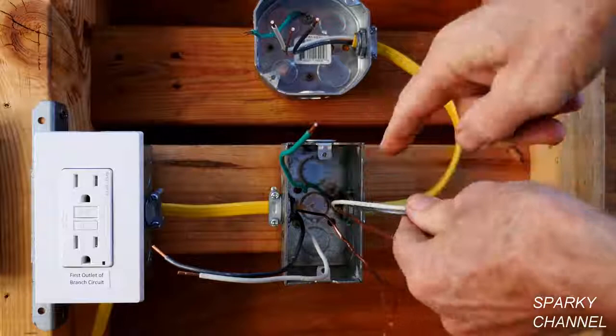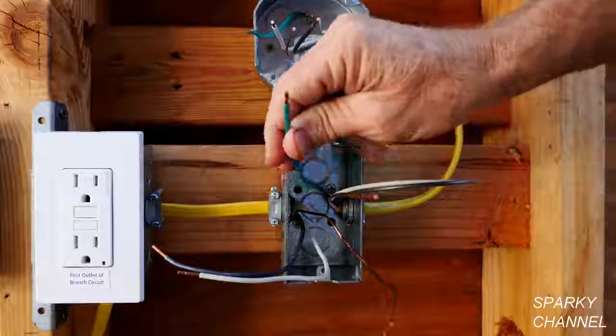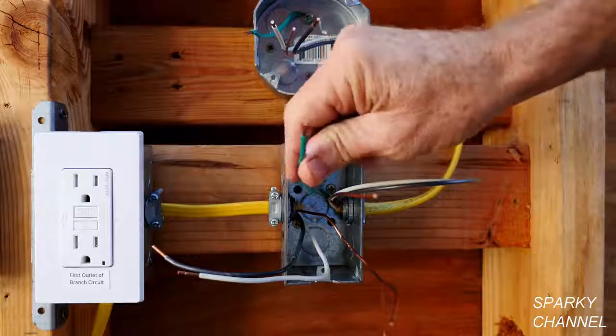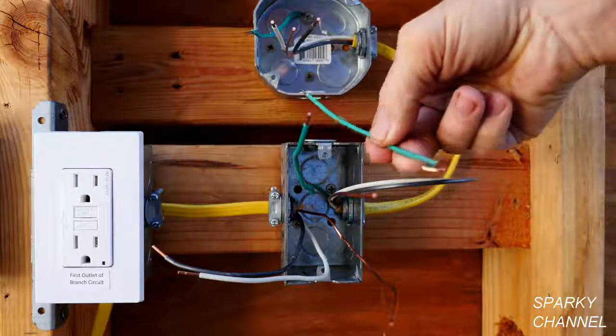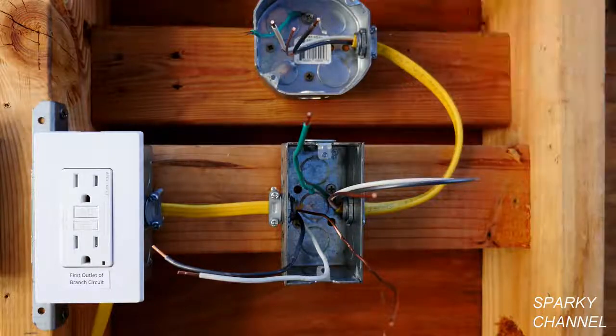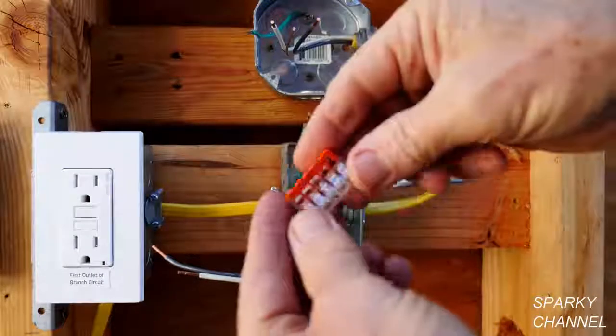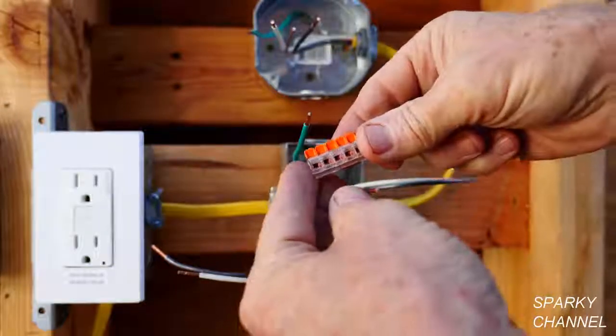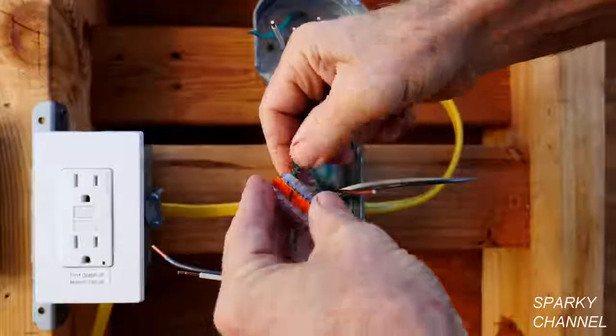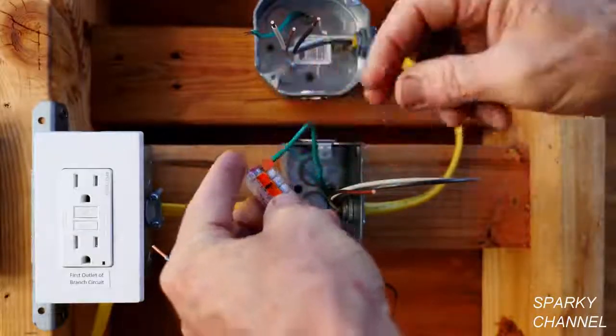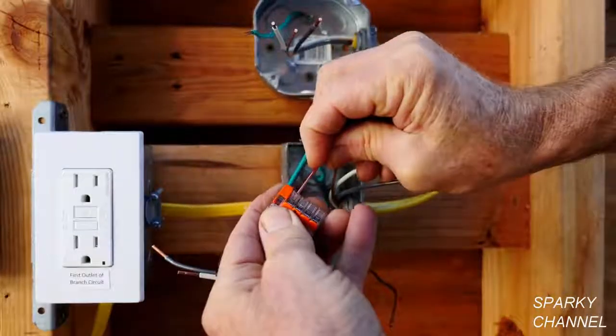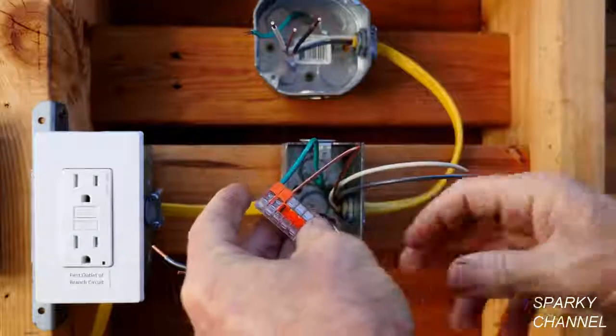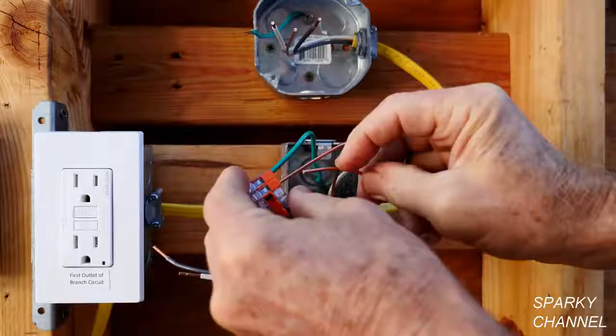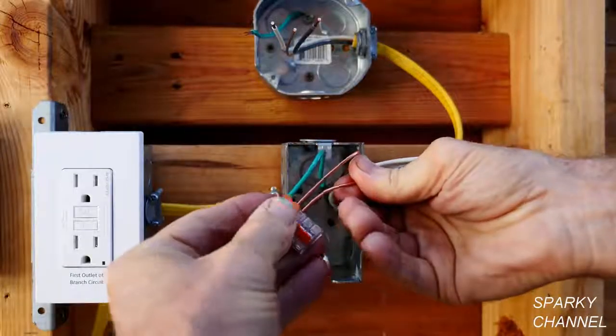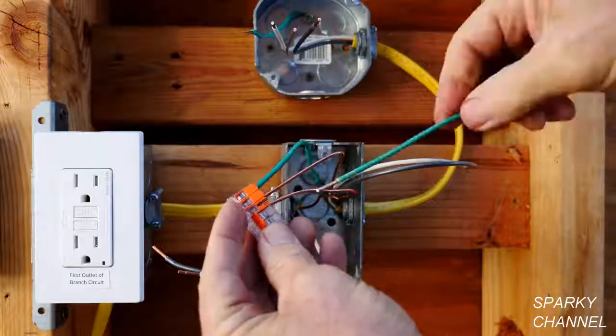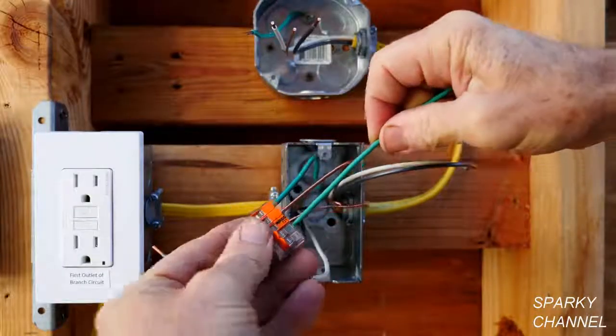It is attached right in here with a screw to the box, and it bonds the box to the grounding system of the house. And I have a pigtail that is going to go to the device itself. To connect these grounds together, I'm going to use a 5 connector Wago lever nut. Take your first connector and put it in the first slot and click down the lever. Then take the next one, put it in the next slot, and again click down the lever. And here we have a third one. Put it in the slot, click down the lever, and now I'll put in the pigtail that I made up for the device and click down the lever.